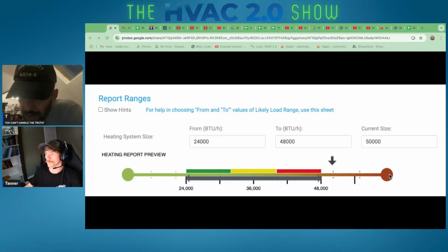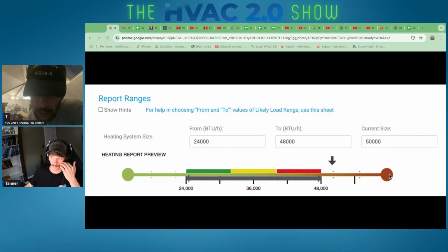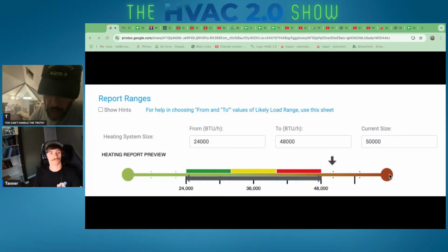Should there be an estimated version and a measured version? And also, should there also be a PSC to ECM motor conversion version? And how would we do that? We talked a little bit about how there probably shouldn't be that 30% factor if it's below half an inch of static, because that 30% factor only starts to come into play when the ECM sees restriction. Yeah.